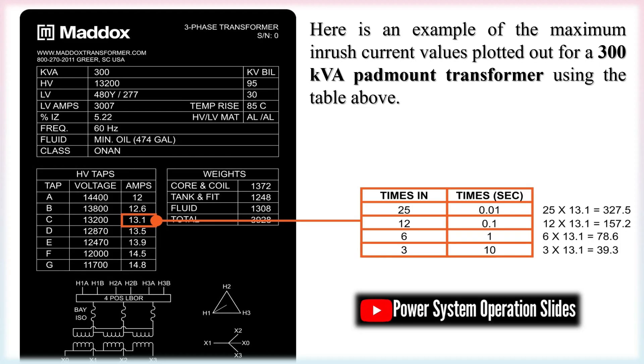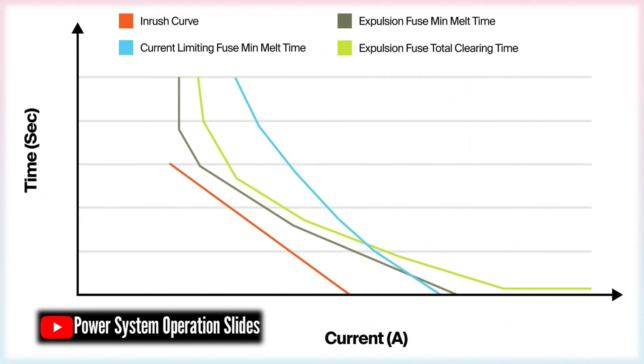Transformer size: The inrush current in a transformer is a brief surge, typically lasting less than a second, that is heavily influenced by the transformer's size and design. Generally, larger transformers draw higher inrush current because they require substantially more energy to magnetize their core. This is analogous to filling a 5-gallon bucket versus an 8-ounce glass. The larger container needs more time and energy to fill, just as a larger transformer needs more excitation current.